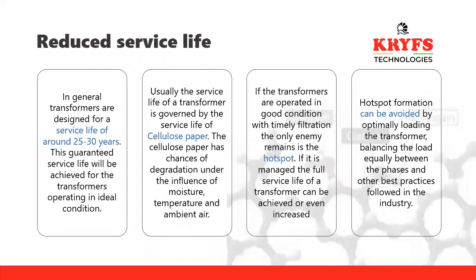Then secondly, the reduced service life. In general, transformers are designed for a service life of 25 to 30 years. This guaranteed service life will be achieved only by transformers operating in ideal conditions. Some of the utilities have even suggested that after 15-20 years a transformer should be decommissioned because old transformers fail very fast. But actually that is not the solution, to change too early, right? If the manufacturer can design a transformer well, it should be that way.